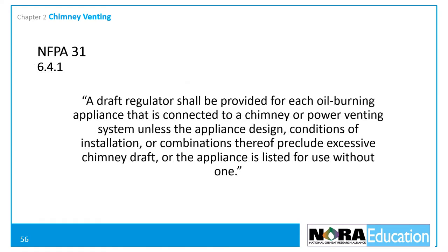The 2020 version of NFPA 31 states: a draft regulator shall be provided for each oil-burning appliance connected to a chimney or power venting system, unless the appliance design, conditions of installation, or combinations thereof preclude excessive chimney draft, or the appliance itself is listed for use without one. Some oil-heat appliances are designed to operate without a draft regulator — their burners create enough static pressure to move combustion products up the chimney, and their heat exchangers are designed to resist strong and variable draft.